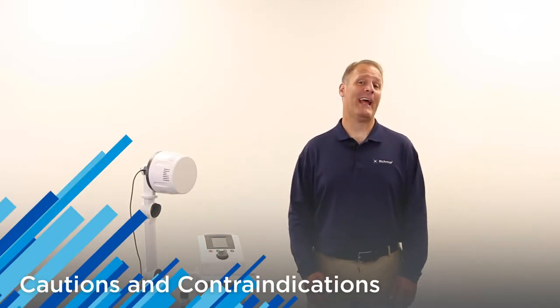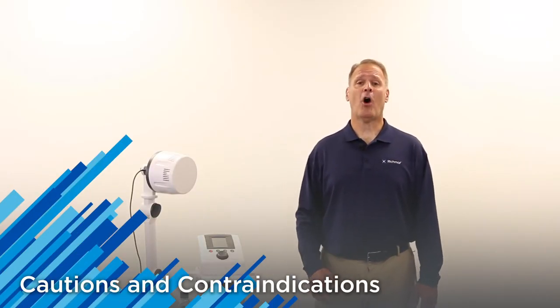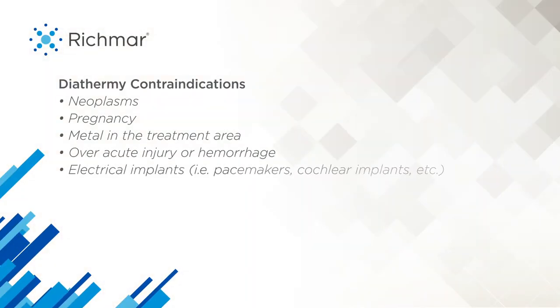As with all modalities used in physical medicine, there is a list of cautions and contraindications for use. Shortwave diathermy is not indicated for use over neoplasms, pregnancy, metal in an area either worn or implanted, or over an acute injury or hemorrhage site.